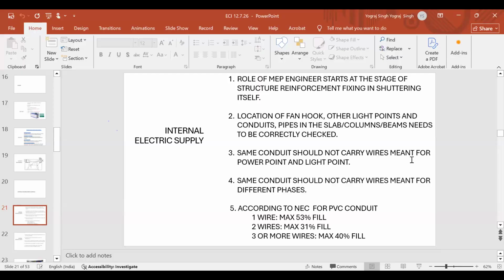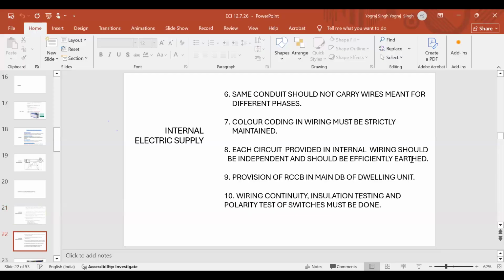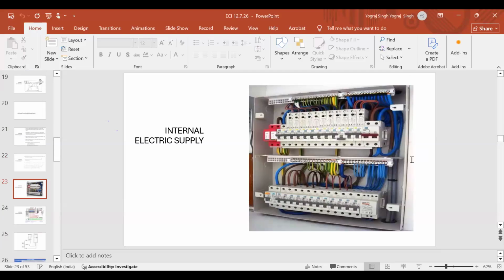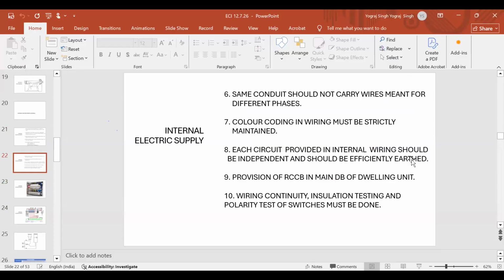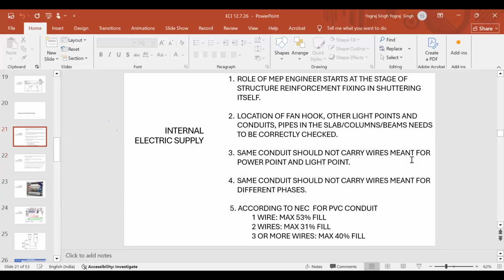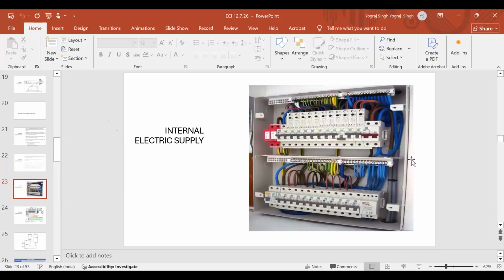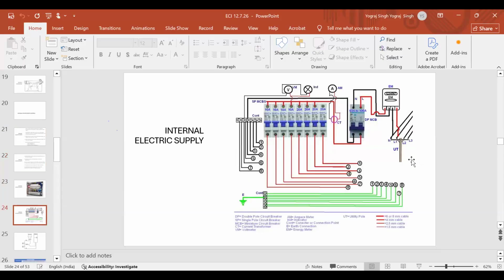Now every house will have power wiring and light fan wiring. For power wiring, the conductor size is different. For light wiring, the conductor size is different. IS says the size of the phase conductor will be 1.5 square mm. In the same way, the neutral conductor will be 1.5 square mm. Earthing will be half the size, which means half of 1.5 is 0.75. But IS also says no conductor should be less than 1.5. That means in my power point and light point, all the conductors will be of 1.5 square mm. Your 16 ampere power point will be fed from 2.5 mm cable.